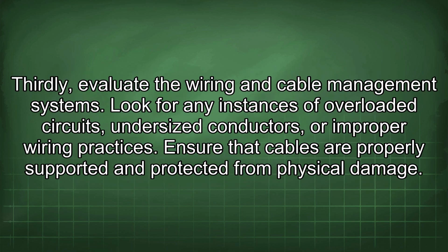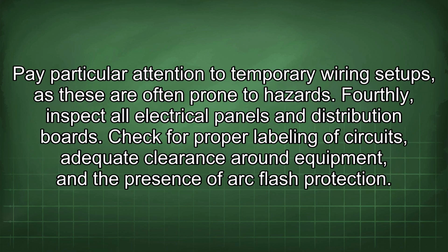Thirdly, evaluate the wiring and cable management systems. Look for any instances of overloaded circuits, undersized conductors, or improper wiring practices. Ensure that cables are properly supported and protected from physical damage. Pay particular attention to temporary wiring setups, as these are often prone to hazards.